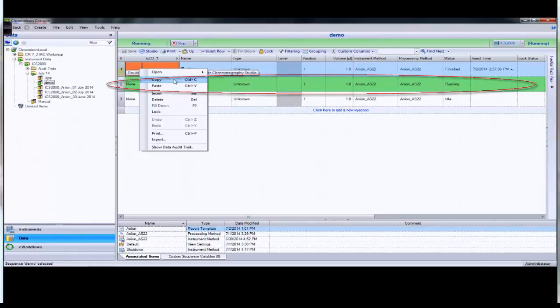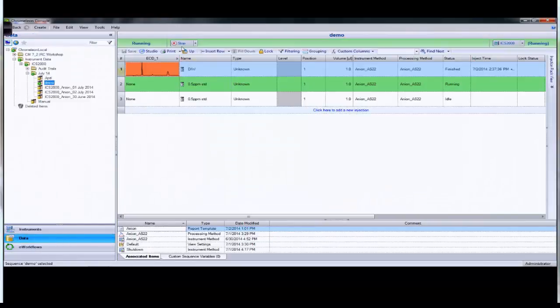However, it's time for us to go home. So go up to the green and hit the stop button. These guys are carrying on, so we can ignore the film. So after you've hit the stop button, then go to the instrument panel and turn the suppressor control off. Then you can click off on the pump switch, and basically you're sorted. What I would suggest is that you actually let the pump run for a little while, just to clear anything out of the system.